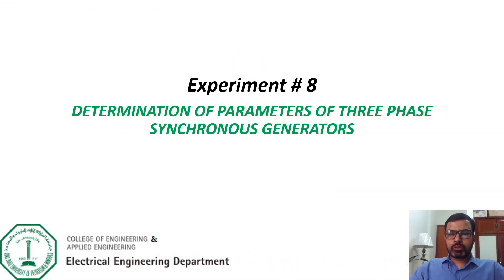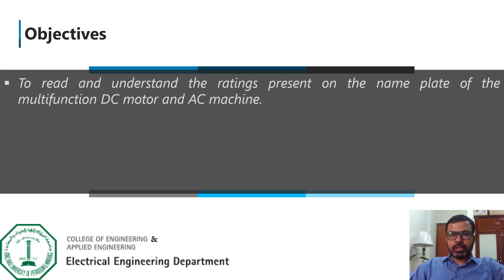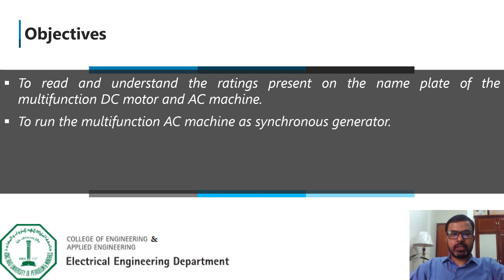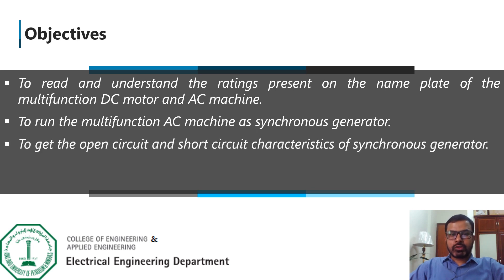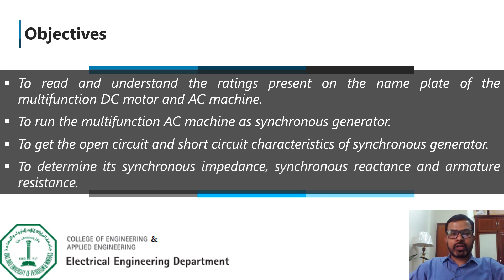Hello everyone. Our today's demonstration is on experiment number 8, where we will determine the parameters of three-phase synchronous generators. The objectives are to read and understand the nameplate data of the DC multifunction motor and AC multifunction machine, to run the AC machine as synchronous generator, to get the open-circuit and short-circuit characteristics, and finally to determine the synchronous impedance, synchronous reactance, and armature resistance of the synchronous generator.